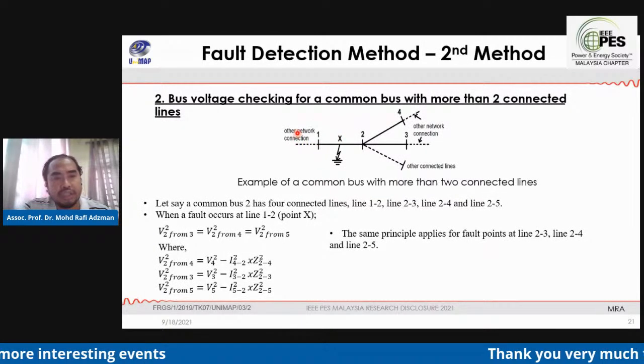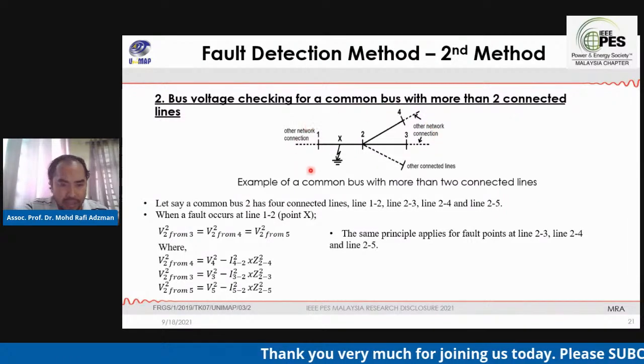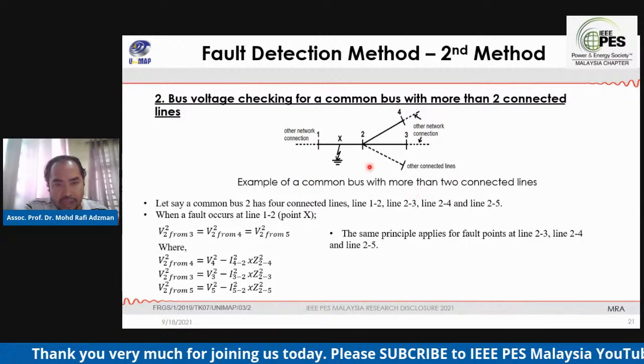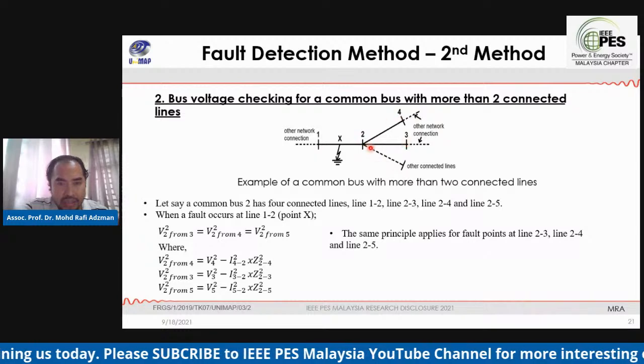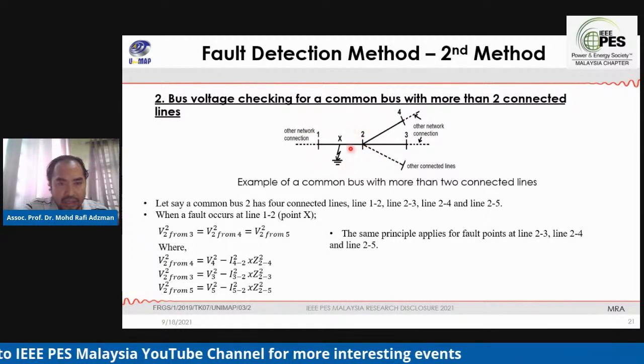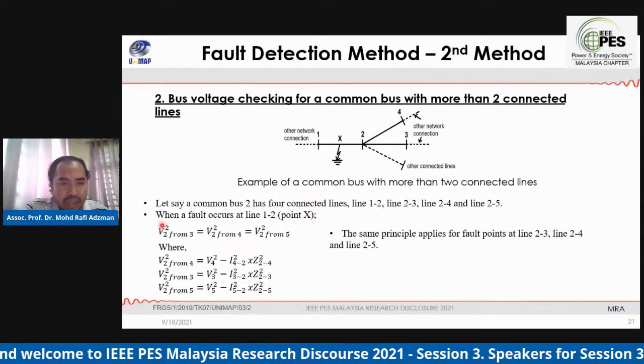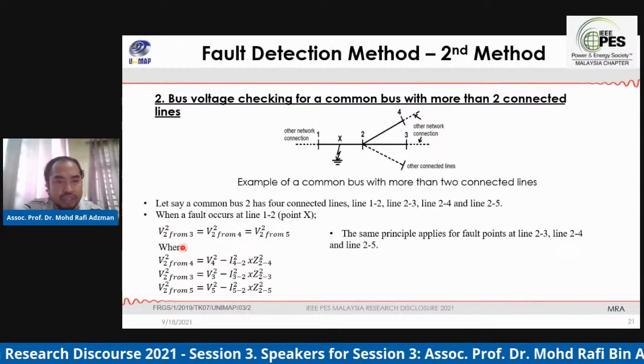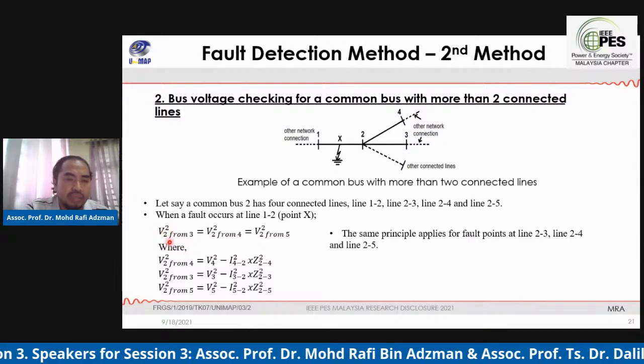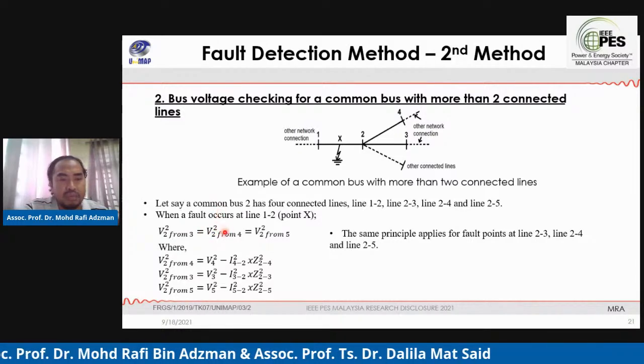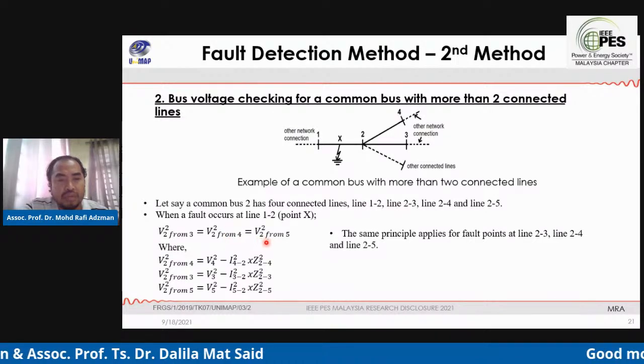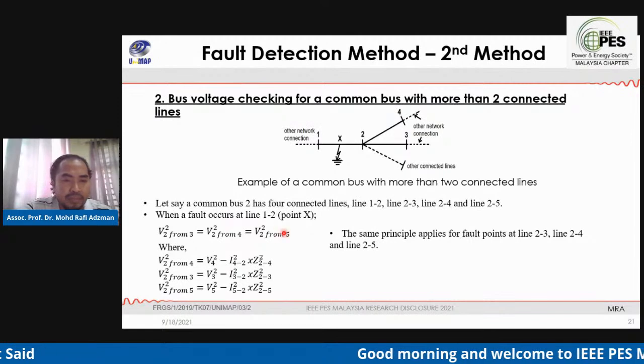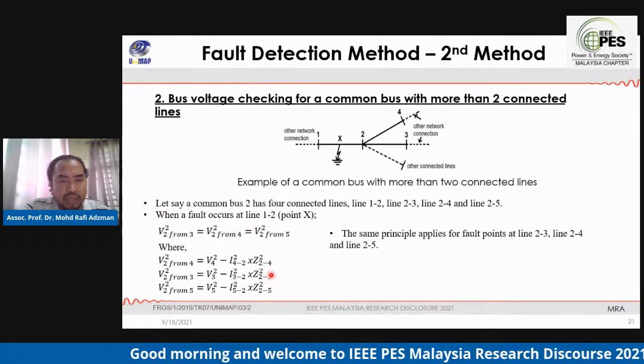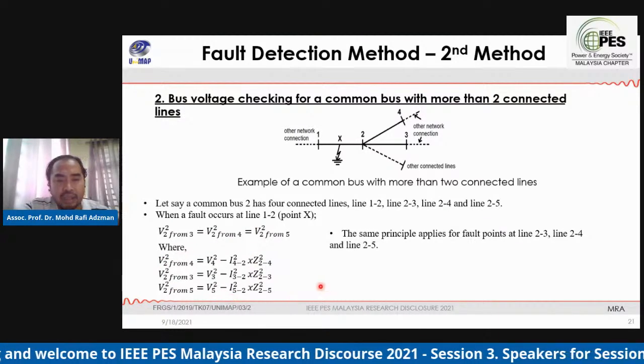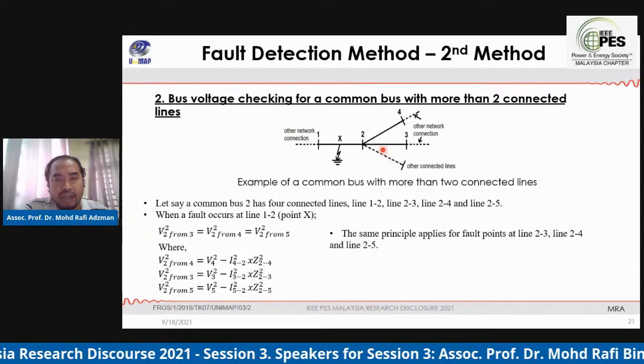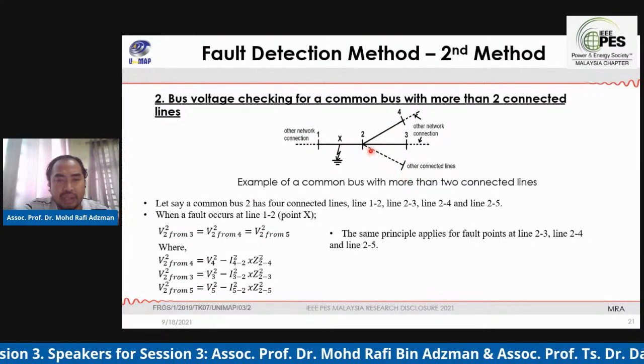Now, bus voltage checking for a common bus with more than two connected lines. Here is an example, with bus 1, bus 2, and other connected lines. When a fault happens on a line, for example line X, the negative sequence bus voltage of bus 2 measured from bus 3 is equal to the negative sequence bus voltage of bus 2 measured from bus 4, and also equal to that measured from bus 5. This negative sequence bus voltage can be calculated using these equations. The same principle can be applied for faults at line 23, 24, and the other lines, for example line 25.